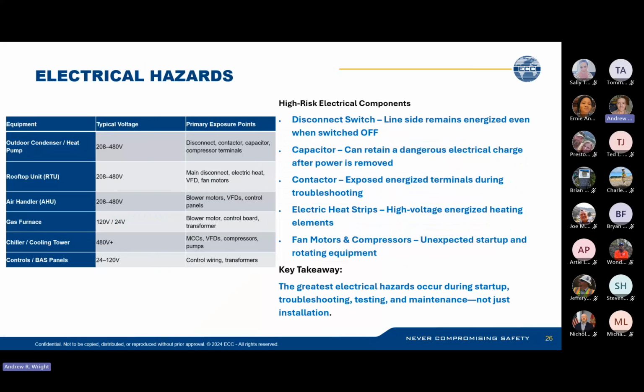All right, electrical hazards. All these systems, one way or the other, run off of electricity and have some sort of electrical component. So your condensers, RTUs, air handlers, furnaces, chillers, and controls all have typical voltage and exposure points. When you open up a panel to add a new line for an HVAC system, or a disconnect switch, all those times you have exposure to electricity. So you've got to make sure that you and your workers are competent in electrical safety.